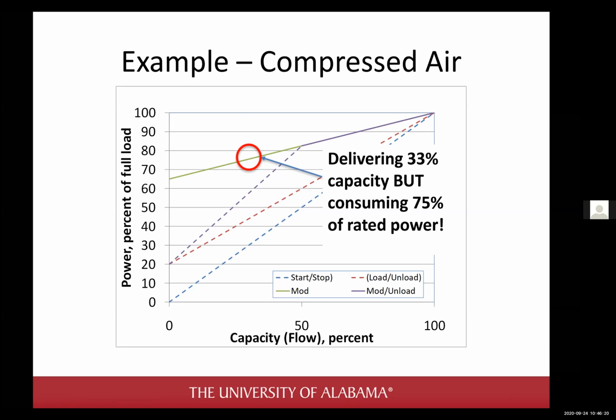So what they do is they just close the inlet valve. Actually, they discharge to ambient. That's what they do. It just loads and unloads. So these screws are either making air to go into the system or they're just blowing air out. Okay, so I'm getting way too deep into the weeds, but all I did was we went up, we changed the control strategy to load unload from modulation.